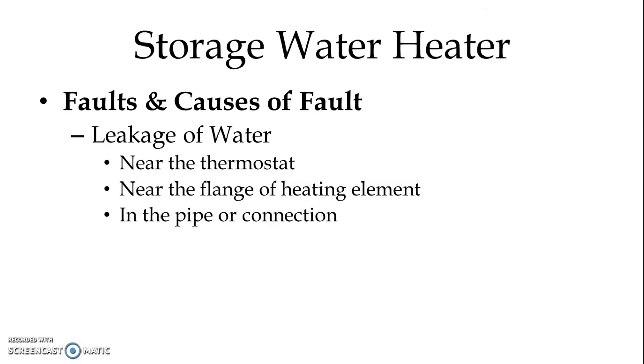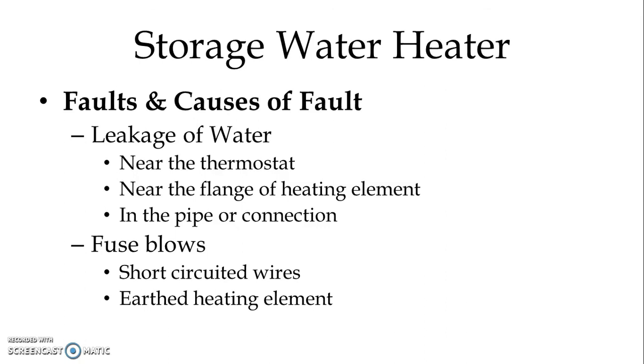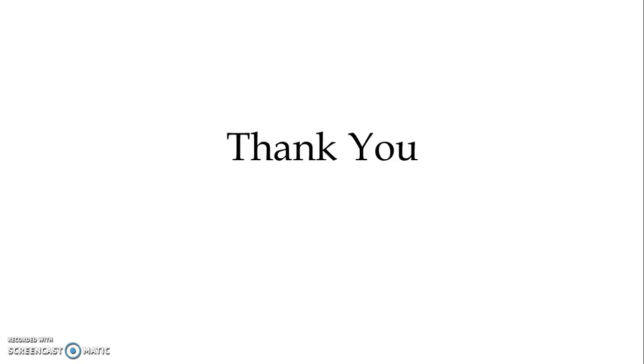We need to identify the exact location of the leakage and rectify it. When we start the storage heater, sometimes the fuse blows. There must be a short circuit in the wire somewhere, or the heating element might be earthed causing an earth fault. So this is all about the two different types of water heaters.